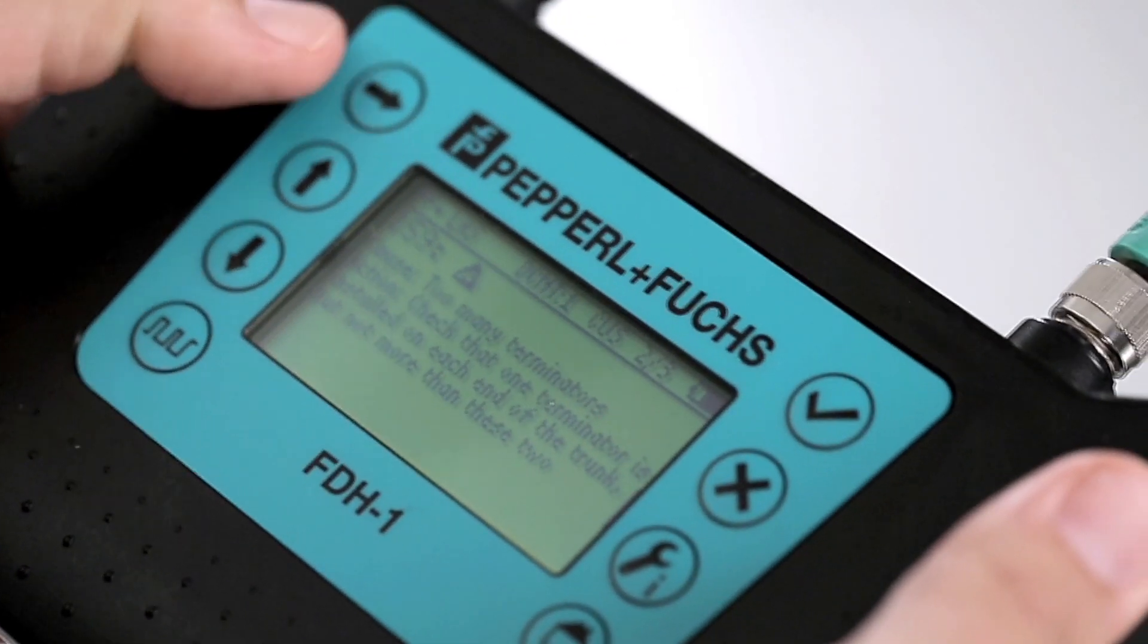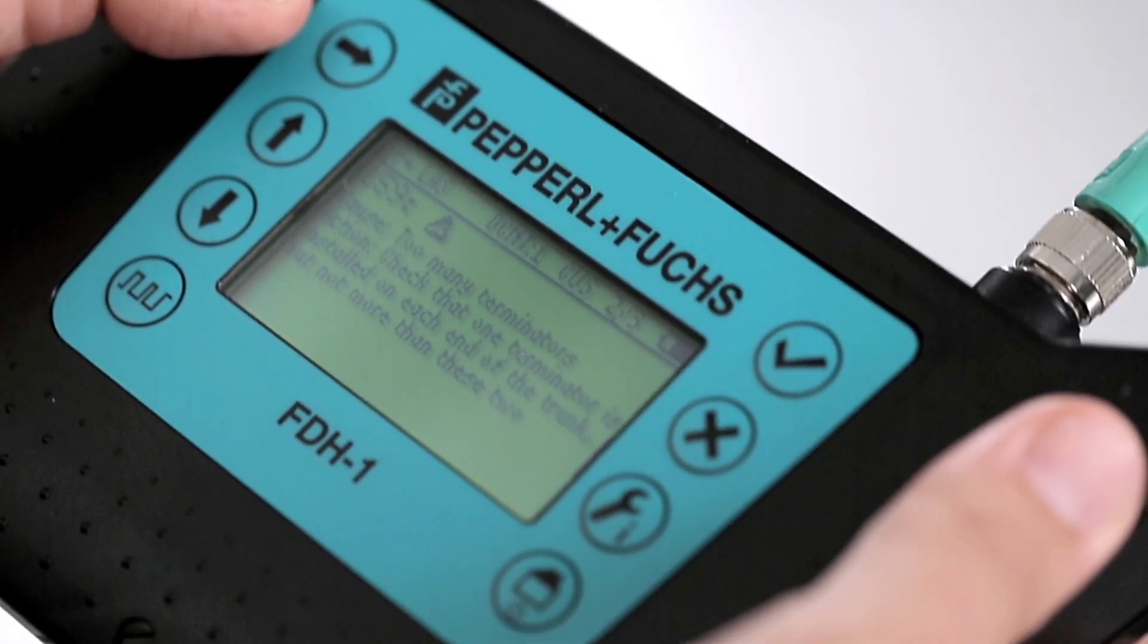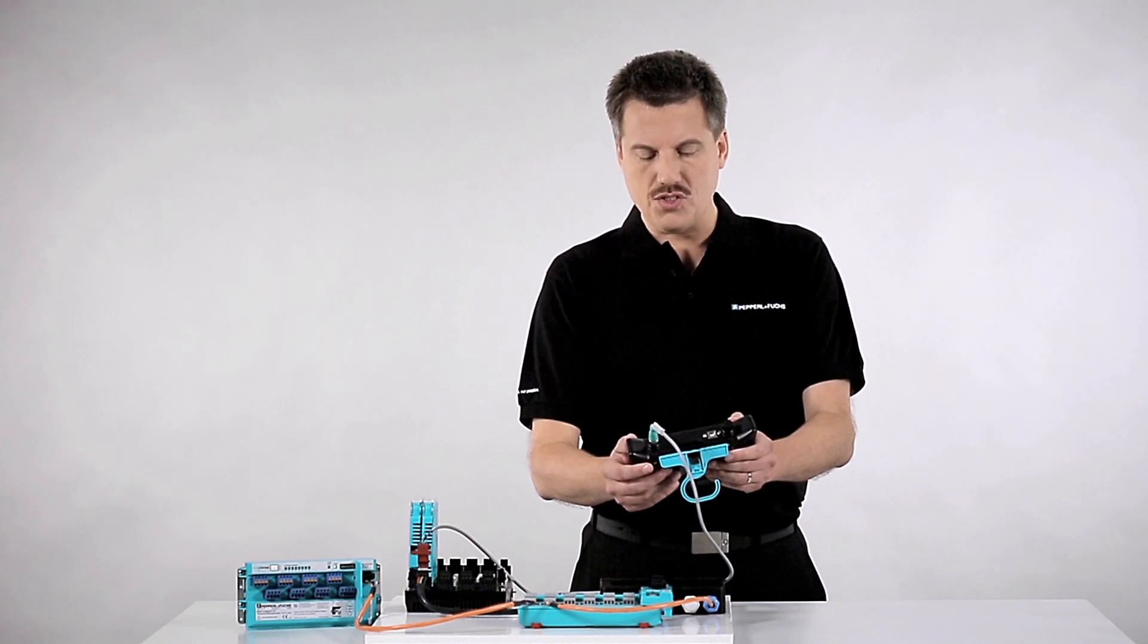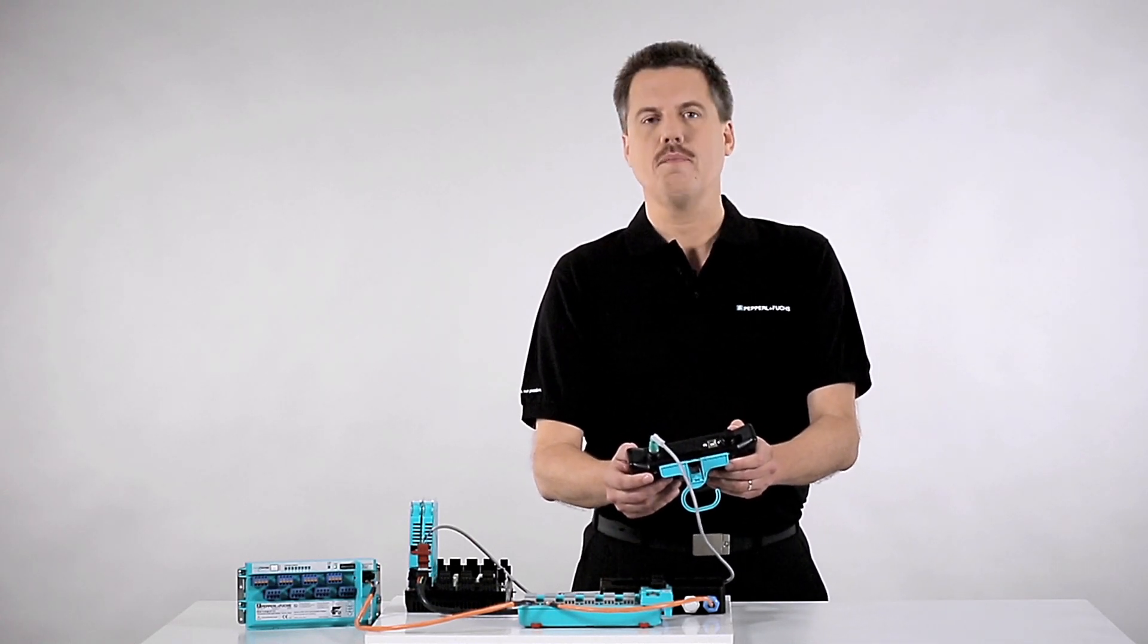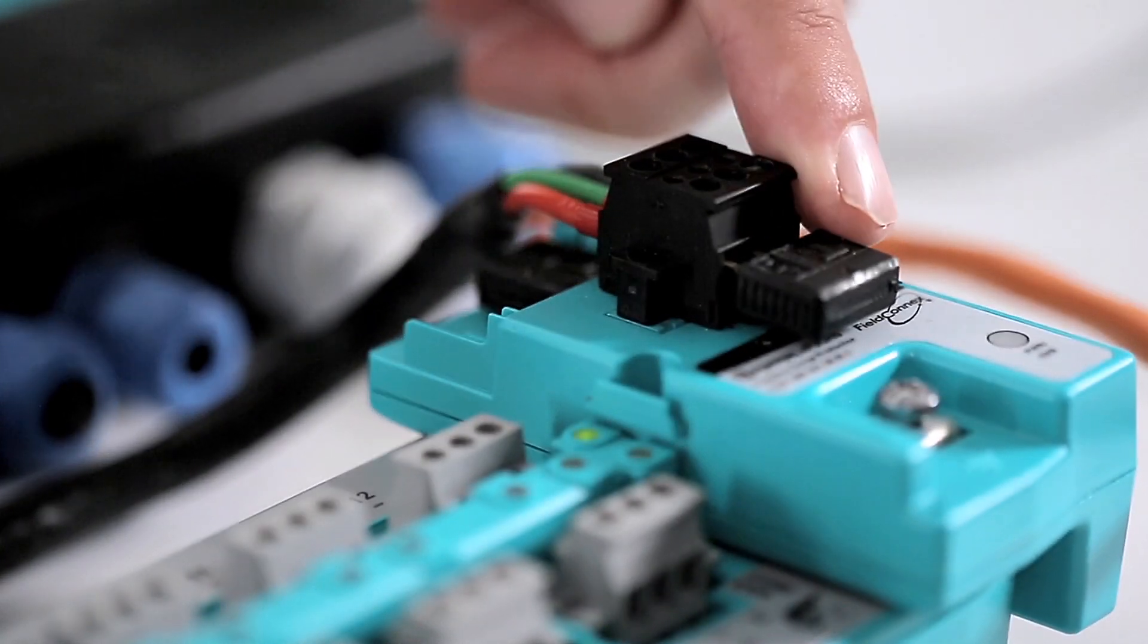Here, a possible cause, too many terminators, and a corresponding action. Check that one terminator is installed on each end of the trunk, but no more than these two. Here is an extra terminator installed.